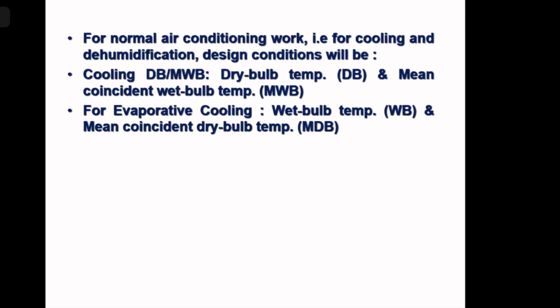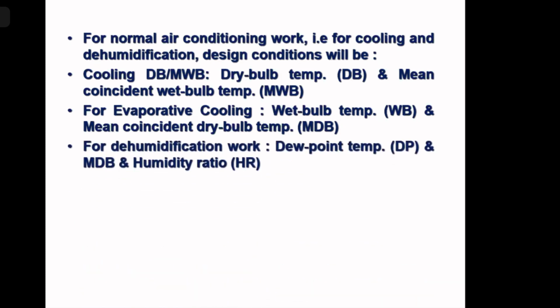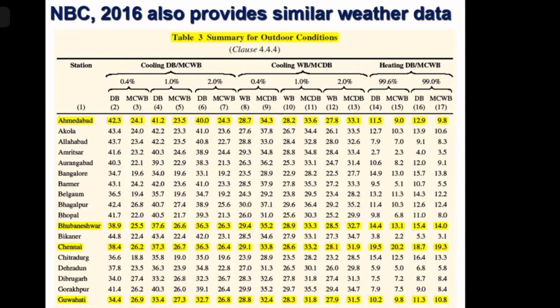For evaporative cooling, we consider the wet bulb temperature and mean coincident dry bulb temperature. You saw the other set of data, evaporative. Those data we have to consider for cooling by air washer or desert cooler kind of thing. And even for sizing the cooling tower, we have to consider that evaporative cooling data given by ISHRAE. Next. For dehumidification work, ISHRAE has also given another set of data with dew point and mean coincident dry bulb and humidity ratio. Those we have to consider. We are not going to discuss dehumidification in detail in this lecture. Next. This is some NBC data, which is older. Similar data. Next.